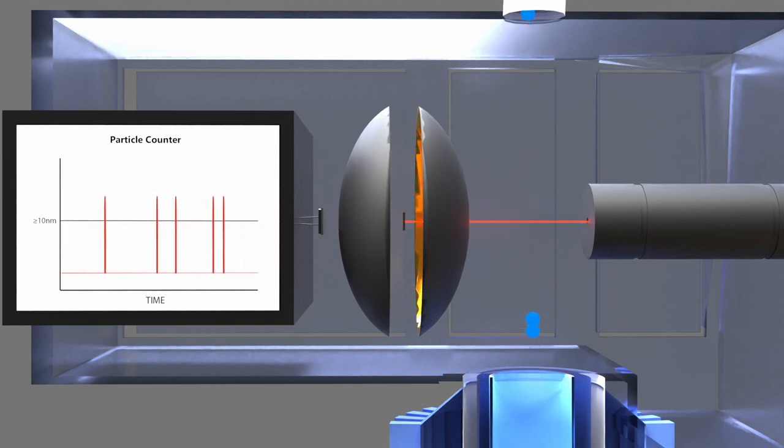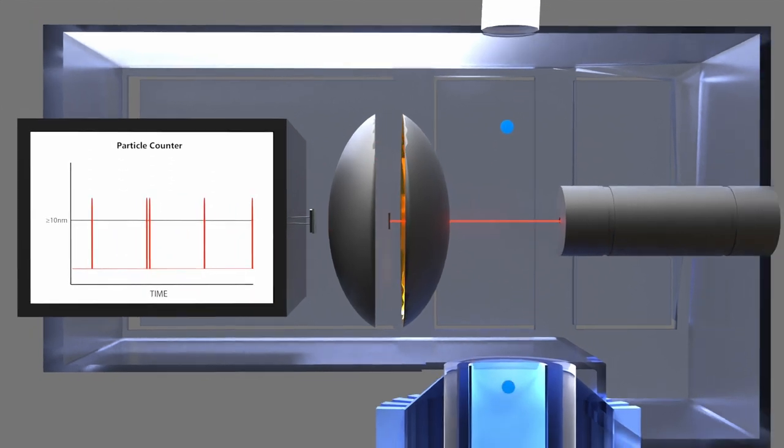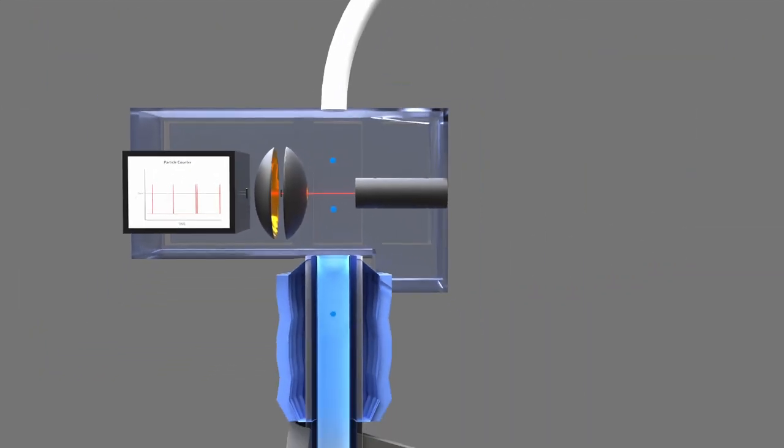Each droplet will generate a distinct pulse, so by counting the number of pulses we can tell, in real time, how many particles are present in the sampled gas.